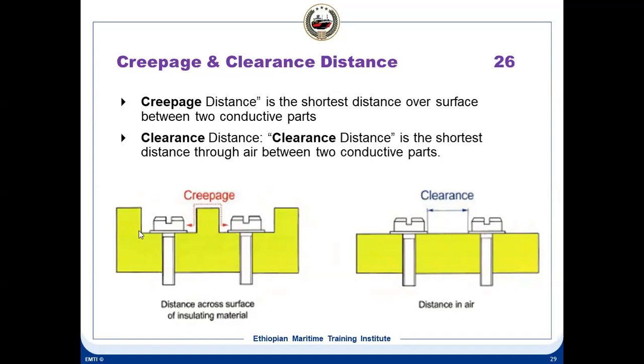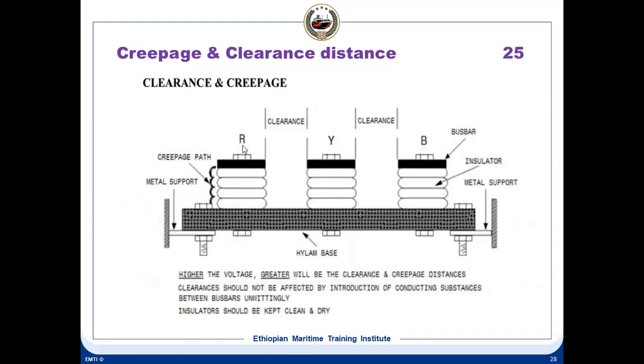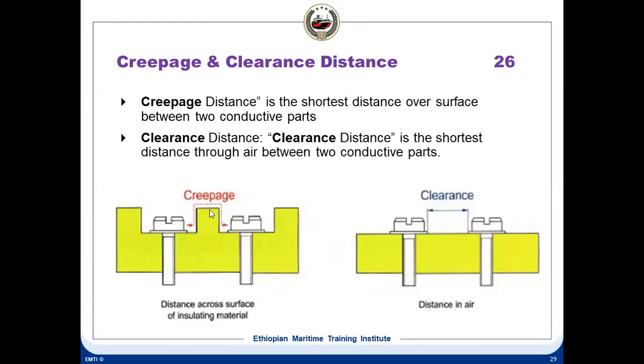Like when you connect two phases RYB, and this is your insulating material, these are the cable connections. In between, how much insulation there is, that is creepage. How much air there is, that is called the clearance. This is where you connect the cables. You see here, you have R phase, Y phase and B phase. The distance in air is called the clearance. This distance is called the creepage path. They have put an insulator here. So this is the creepage, this is the clearance.